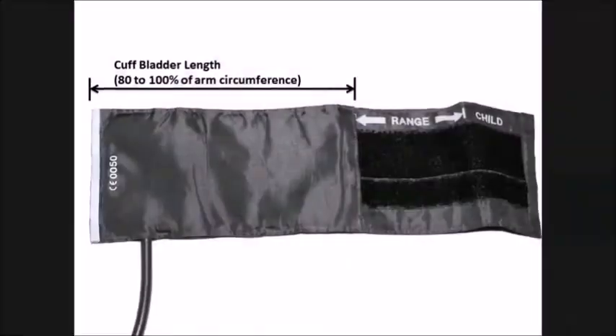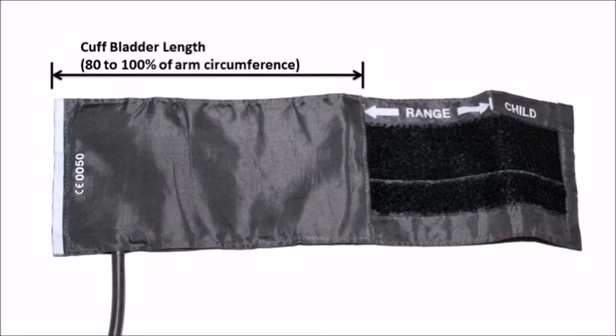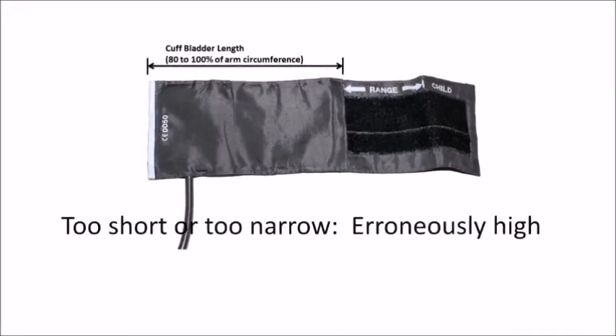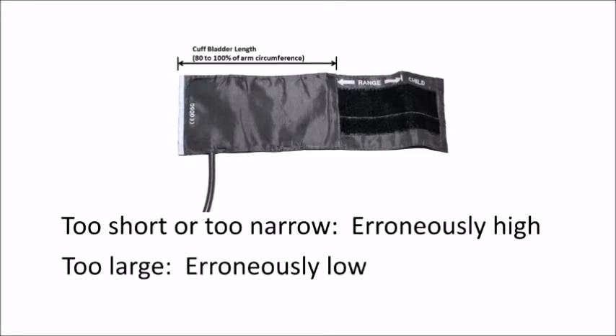When a cuff fits appropriately, the inflatable bladder should cover about 80% of the circumference of the patient's arm. Using a cuff that is too short and narrow results in erroneously high blood pressure measurement. When a cuff is too large, blood pressure measurements will be erroneously low.